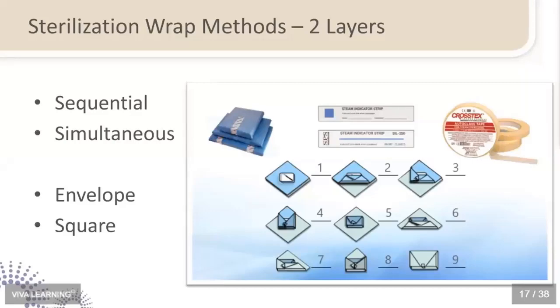It is going to be important that a chemical indicator is put inside the cassette with the instruments before it's wrapped. And because that wrapping is opaque, you can't see the chemical indicator, you need to also have a chemical indicator on the outside of the wrap, CDC guideline.